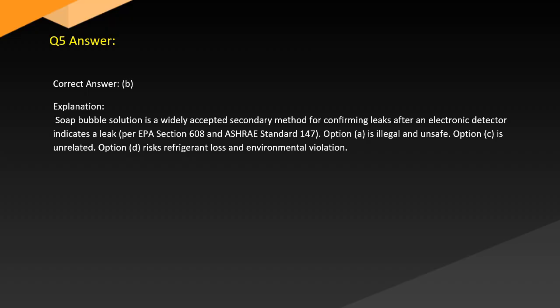Answer. Correct answer: B. Explanation. Soap bubble solution is a widely accepted secondary method for confirming leaks after an electronic detector indicates a leak, per EPA Section 608 and ASHRAE Standard 147. Option A is illegal and unsafe. Option C is unrelated. Option D risks refrigerant loss and environmental violation.